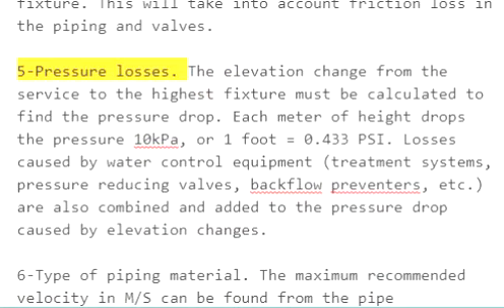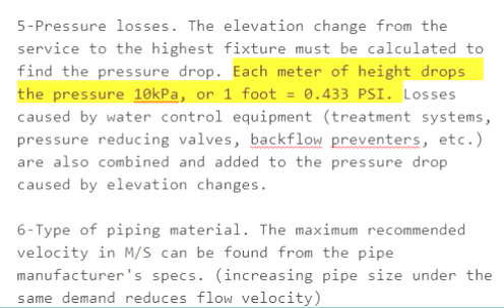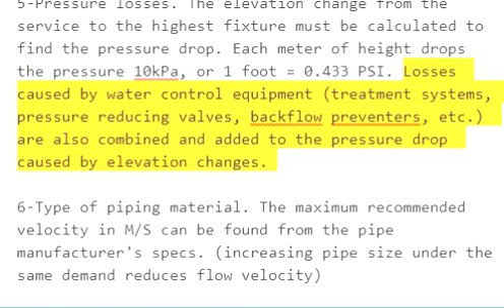5. Pressure losses. The elevation change from the service to the highest fixture must be calculated to find the pressure drop. Each meter of height drops the pressure 10 kilopascals, or 1 foot equals 0.433 psi. Losses caused by water control equipment, treatment systems, pressure reducing valves, backflow preventers, etc., are also combined and added to the pressure drop caused by elevation changes.